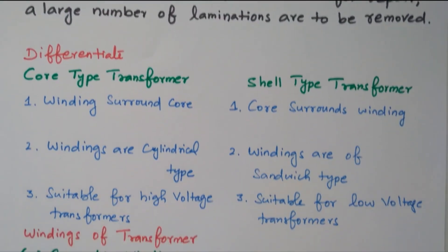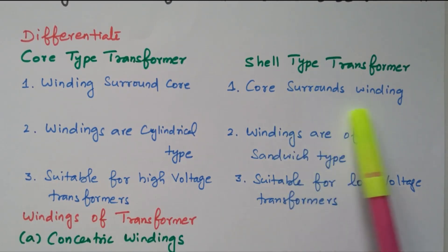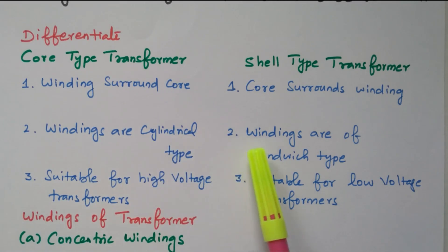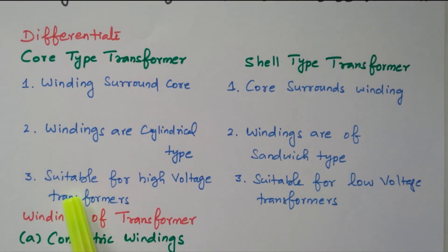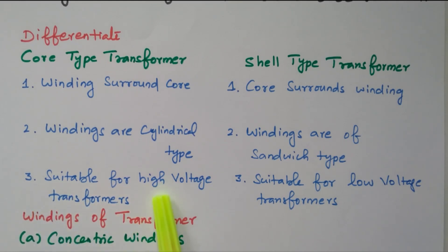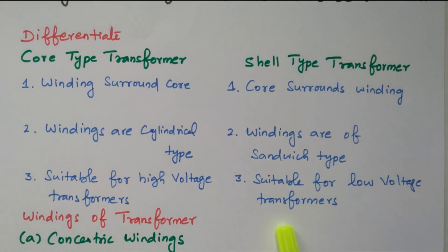Comparing the two types: in core type, windings surround the core; in shell type, core surrounds the winding. Core type uses cylindrical windings, shell type uses sandwich windings. The core type is suitable for high voltage transformers because the two windings are on two different limbs — primary on one end, secondary on another — with no physical contact, only magnetically coupled. The shell type is suitable for low voltage transformers, as one winding is placed over the other, creating a possibility of short circuit.